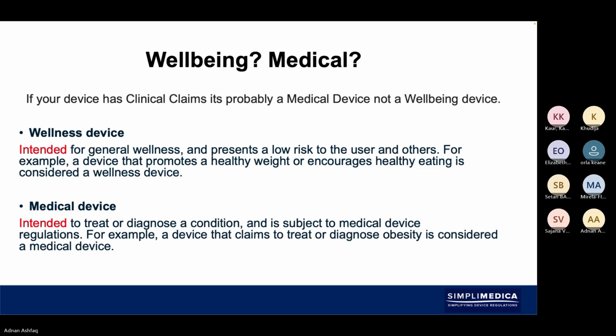actually is. So this question often comes whether the medical device is in fact a wellness or well-being device, because some devices which do not have clinical claims may not actually be a medical device. So it's then the intended purpose which outlines whether the device in fact needs to undergo the medical device regulations and directives, or if it's going to undergo a different route of conformity, which may be for consumer use. It might be under the electrical directives. It could be for other consumer products, etc. And so there's a whole number of other things.